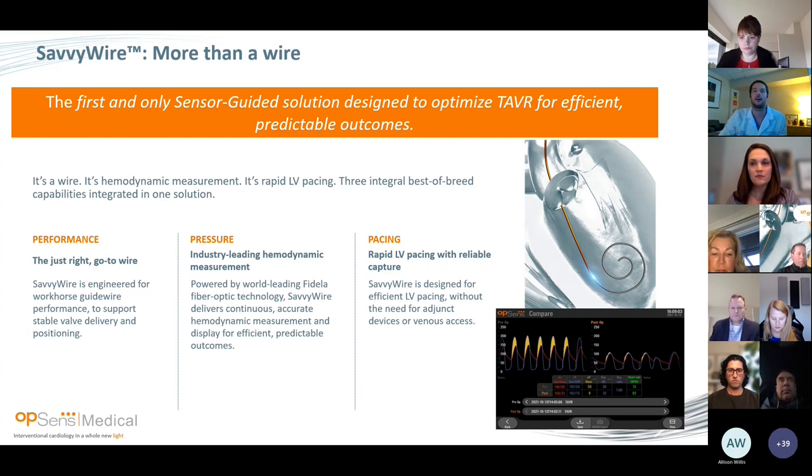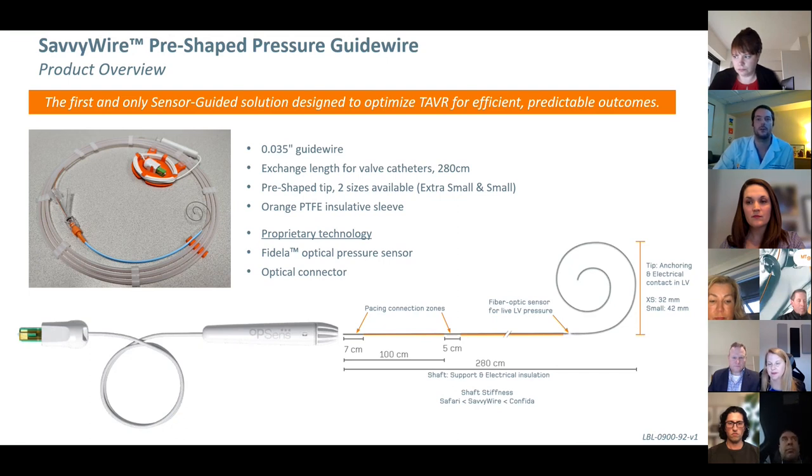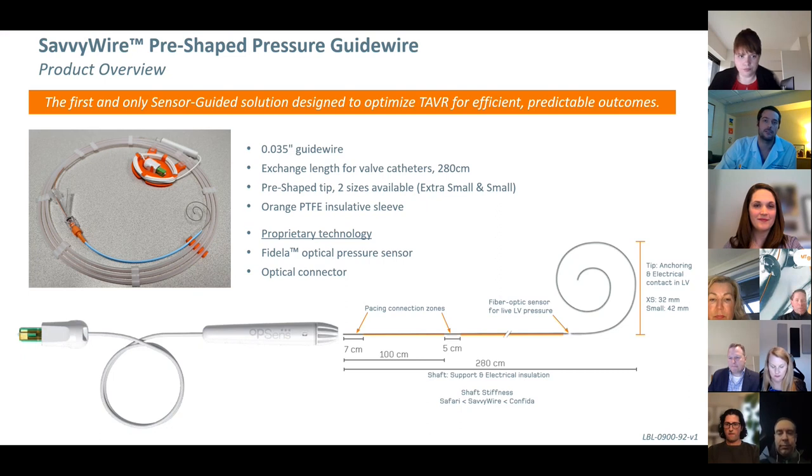This is our device. It's pre-shaped with a nice little curve at the end. It's clearly the first wire to have a fiber optic sensor embedded to give continuous LV pressure. It's 0.035 inches, same as any other wire, but a little bit longer at 280 cm to ensure pacing capability and a nice valve exchange. It's bright orange with a PTFE sleeve coating, which increases conductivity for pacing. Key is the Fidela sensor at the tip of the wire, and then optical connectors very similar to your OptiWire in FFR — simply connect at the proximal end to have your reading.